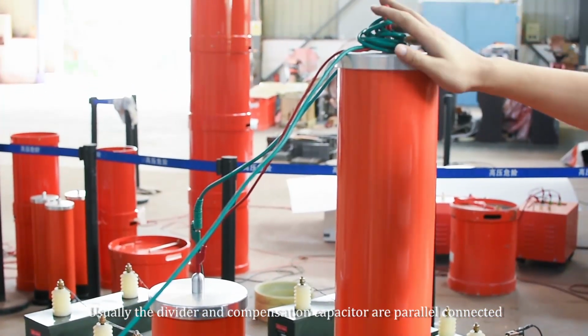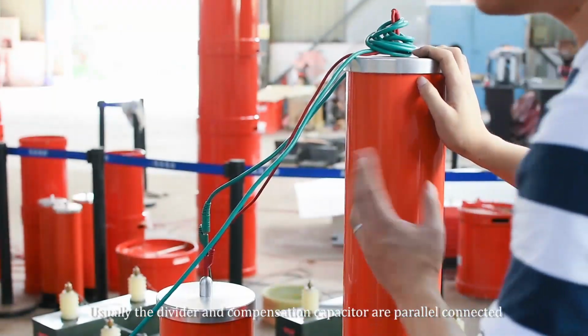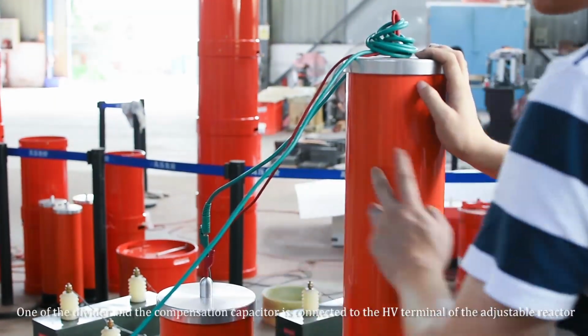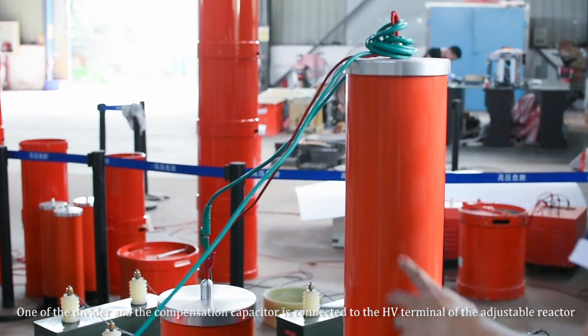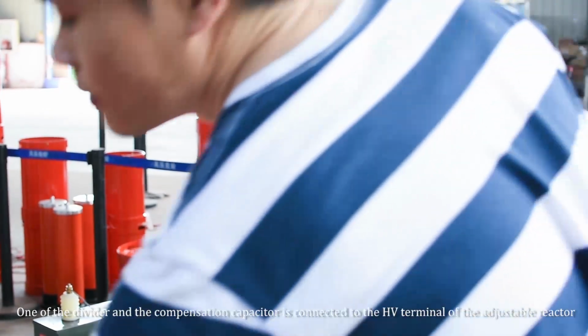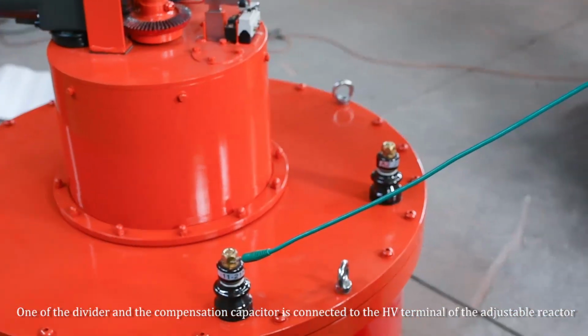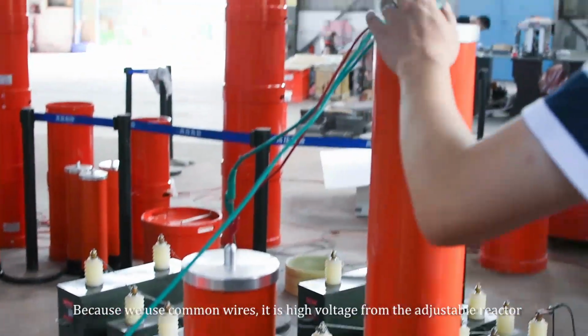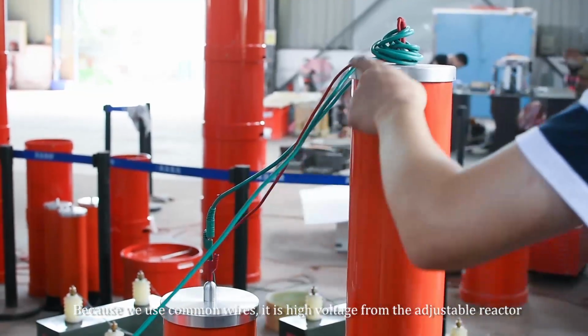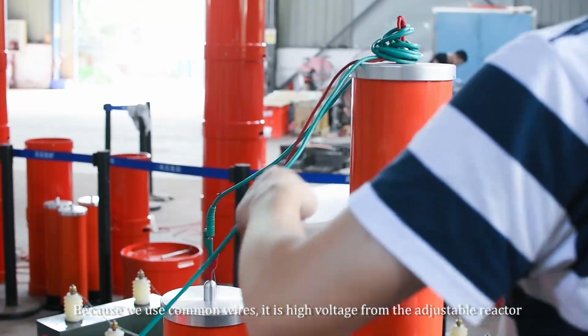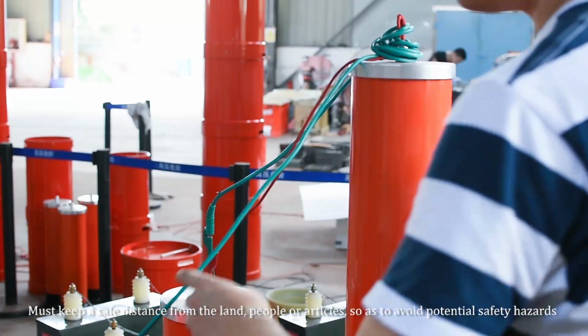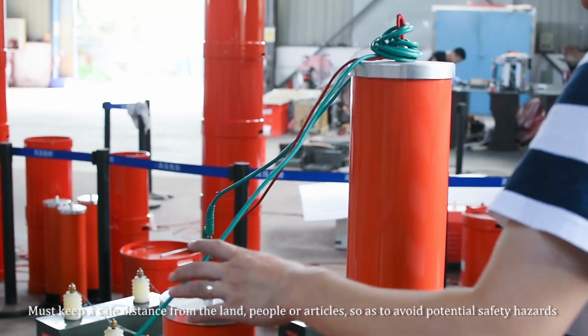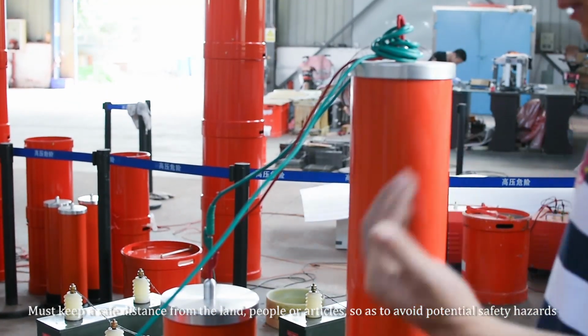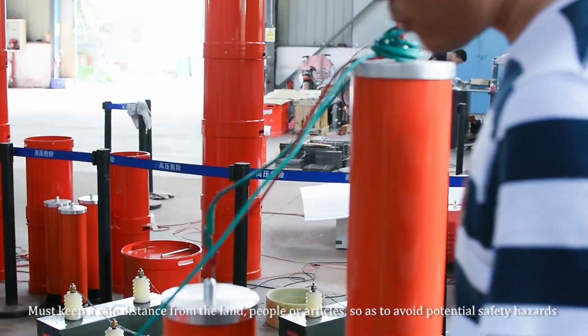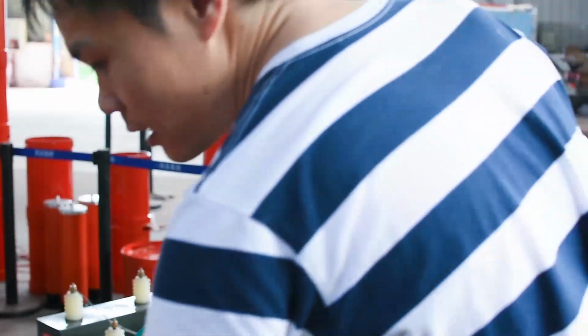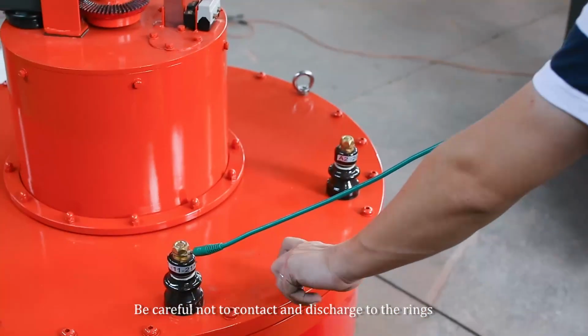Usually, the divider and compensation capacitor are connected in parallel. One of the divider and the compensation capacitor is connected to the HV terminal of the adjustable reactor. Because we use common wires, it's high voltage from the adjustable reactor. Must keep a safe distance from the land, people, or articles so as to avoid potential safety hazards. Be careful not to contact and discharge to the rings.